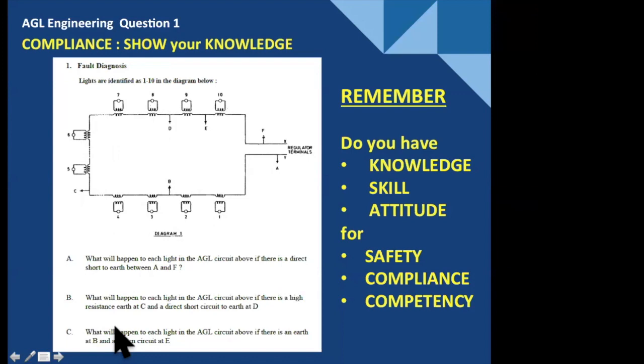What will happen to each light when there is an earth at B and an open circuit at E? Open circuit means no current can flow anywhere, so the CCR will trip out, and all lights 1 to 10 will be off. Simple as that.